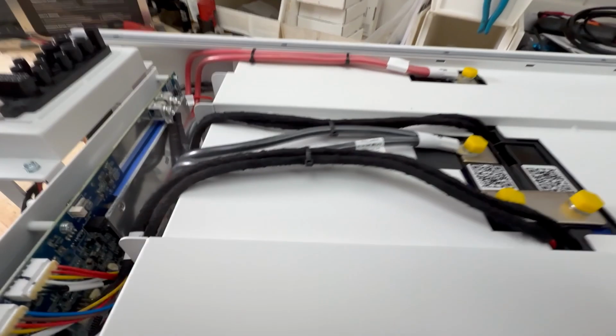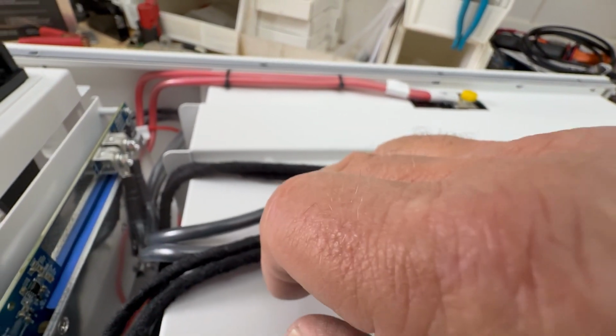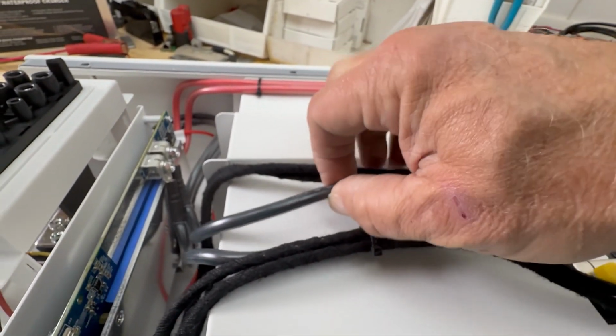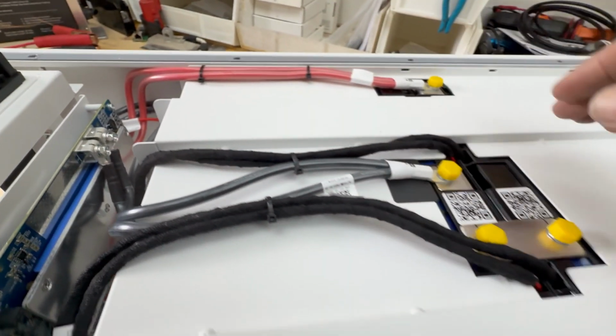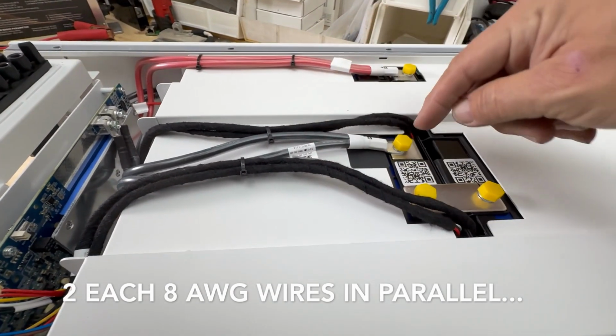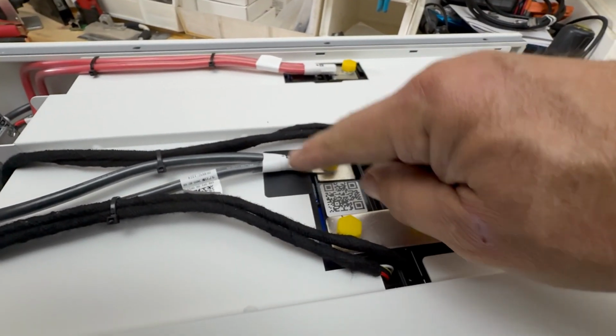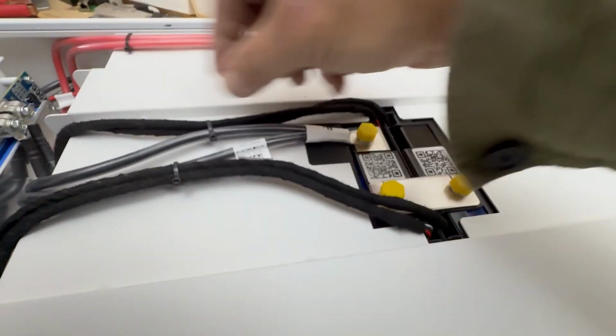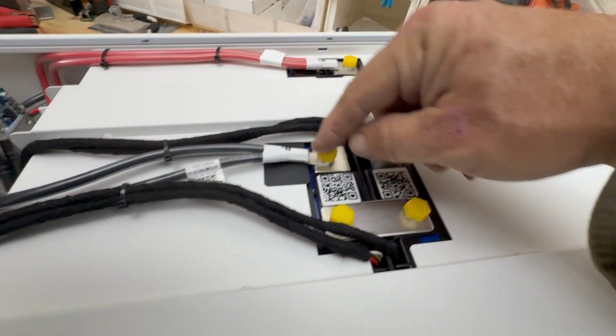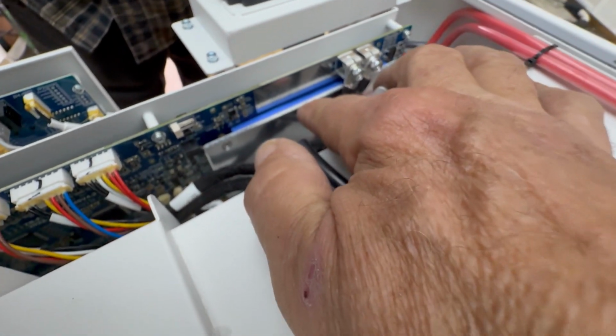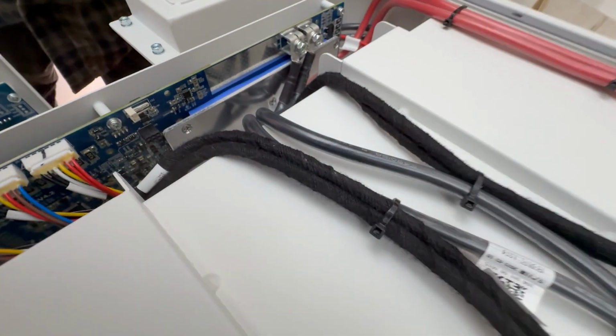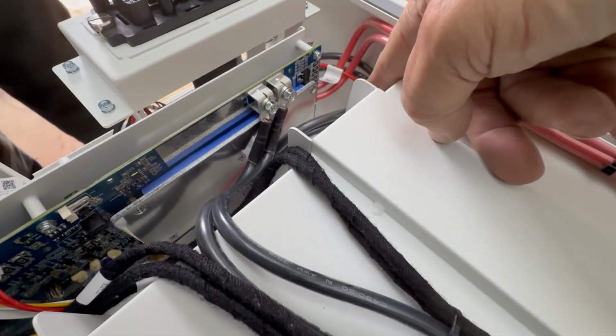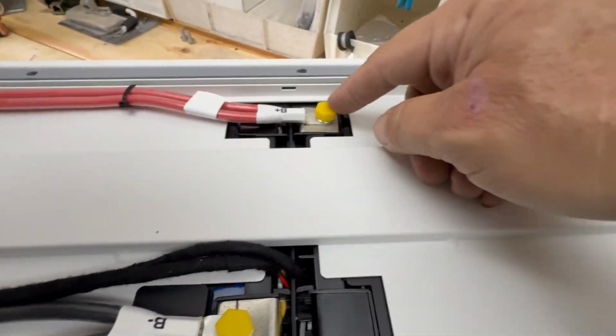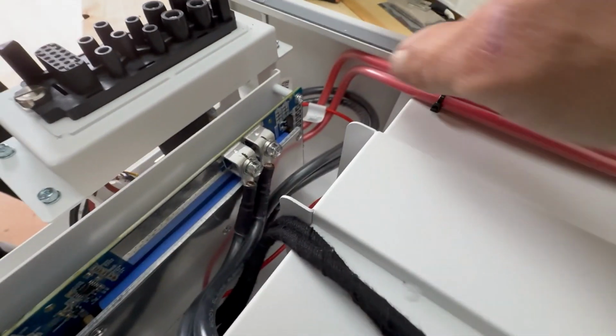BMS, battery management system. We have parallel 8-gauge cables. Parallel - oh yeah, you mean so the way they run? Yeah, this 8-gauge cable is paralleled. It's parallel, right? And so this one's crimped into one lug. That goes over to our FET array for turning on and off the battery bank - the coming in of the negative conductor and the leaving of the negative conductor, the positive conductor going to here.